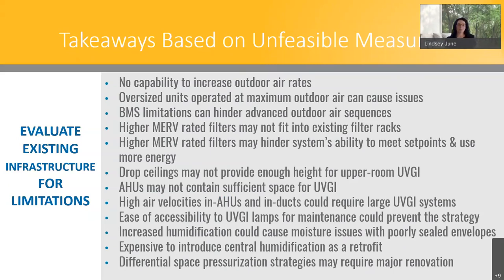In air handling unit or in-duct UVGI may be too costly to implement for the required system size in order to provide sufficient dosing due to high air velocities. And then consider the ease of installation and maintenance for UVGI installations, such as accessibility to lamps for changeouts. In duct particularly could be challenging, or where MERs serve as the mixed air plenum with low air velocities, it's easier to install UVGI there than say in air handling units upstream of coils. But where those systems are easily accessible, UVGI safety precautions especially need to be implemented to prevent exposure.